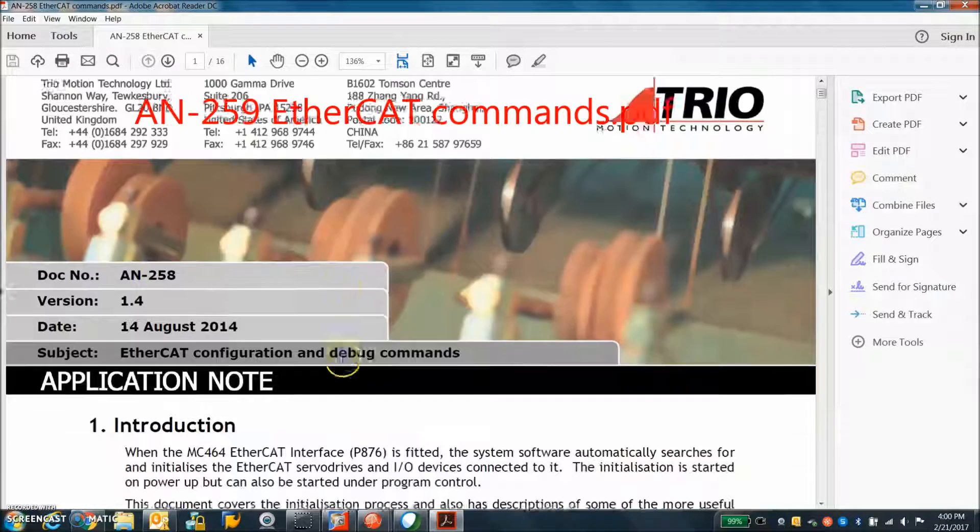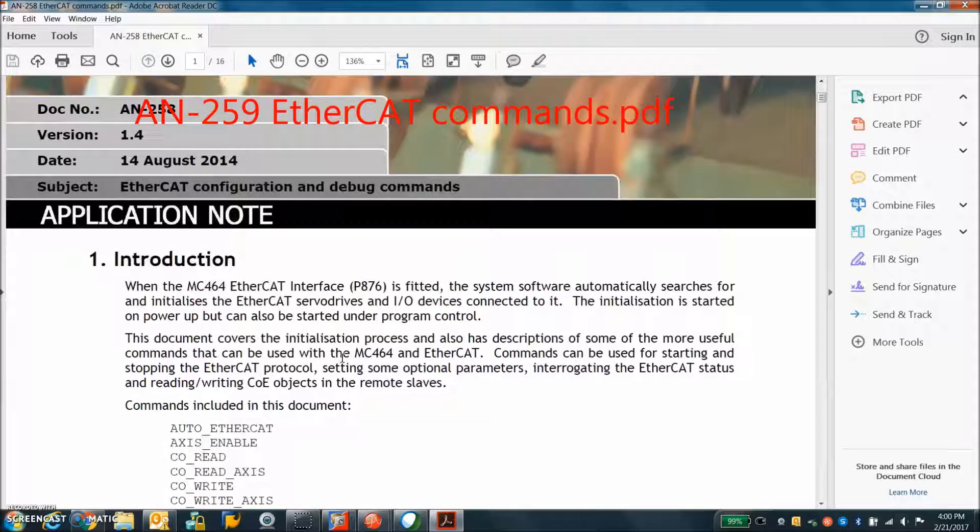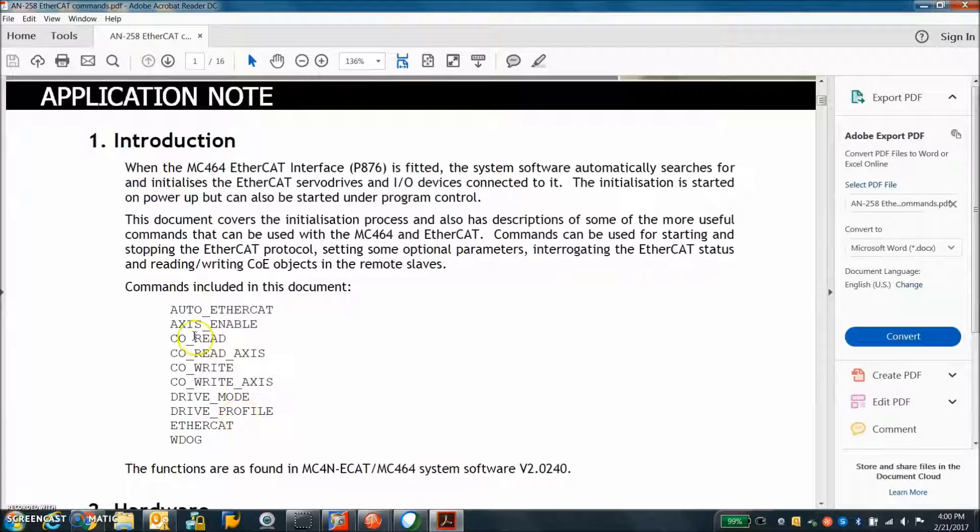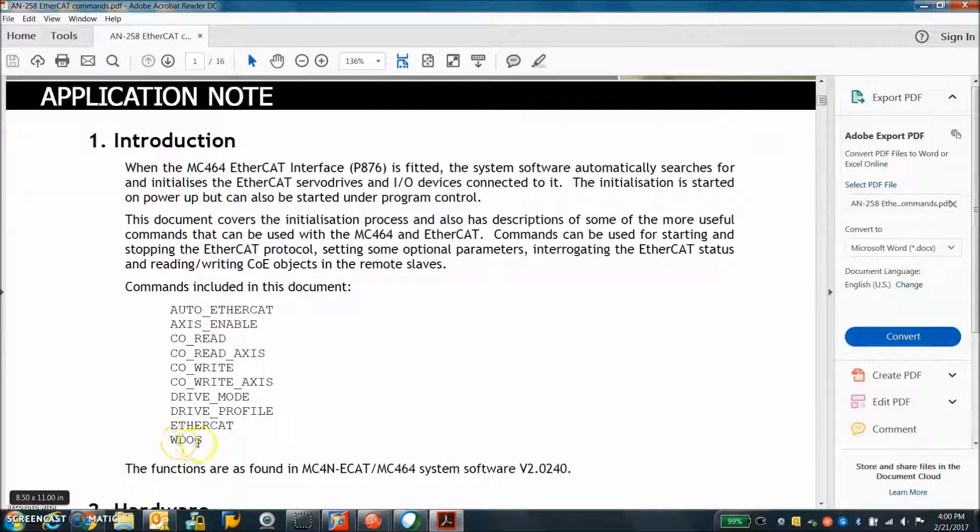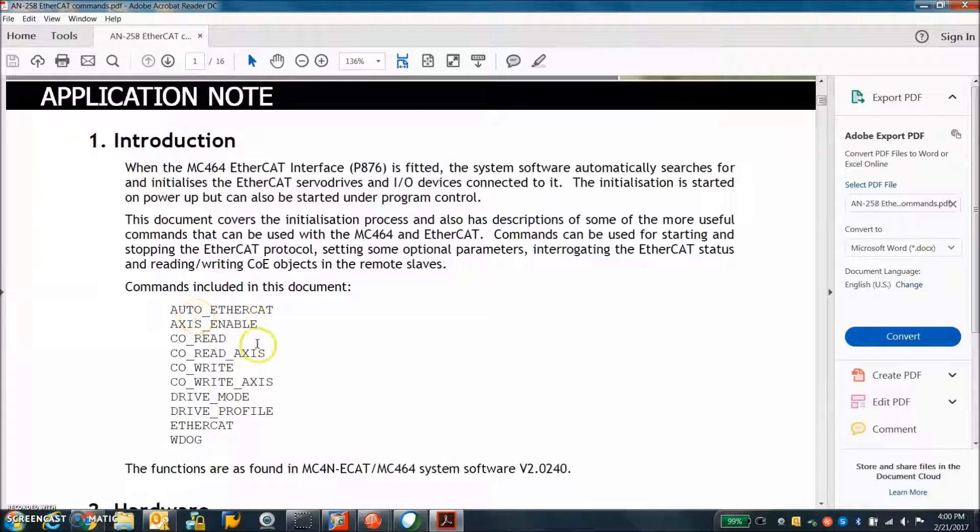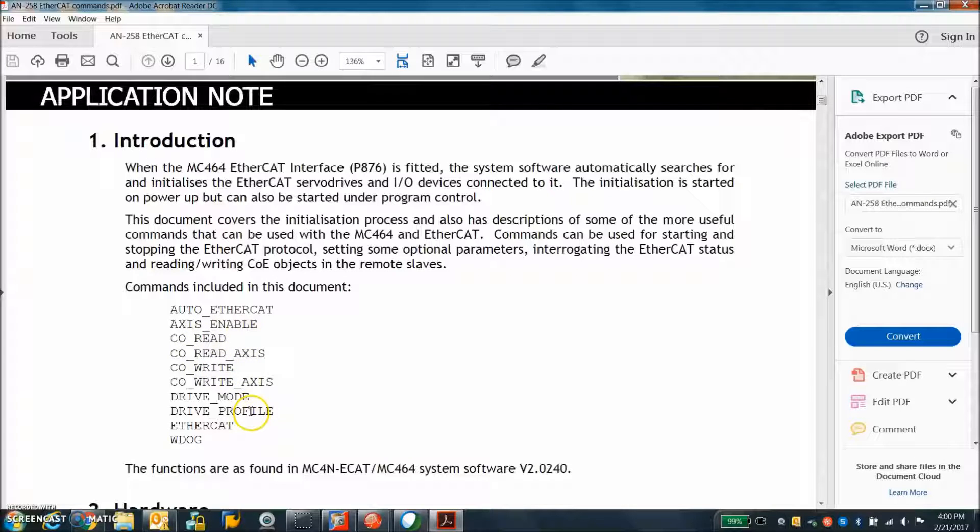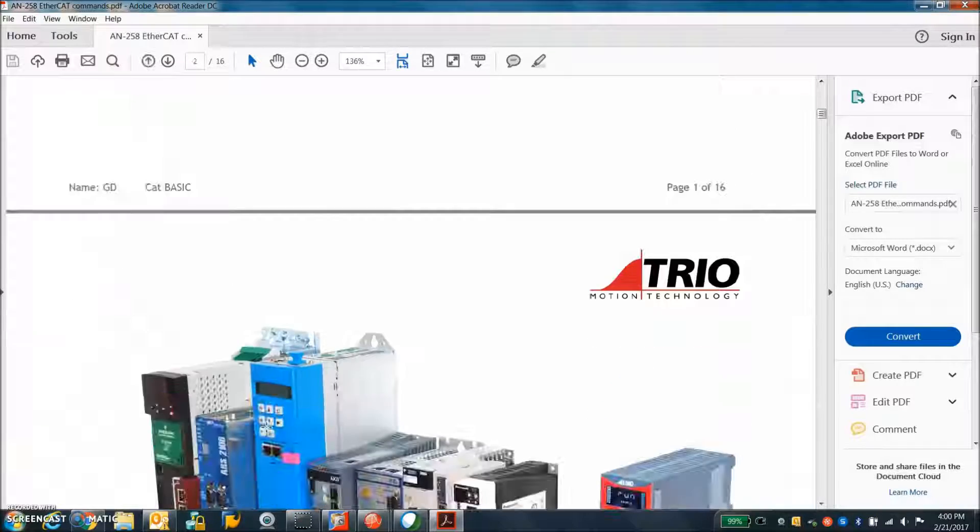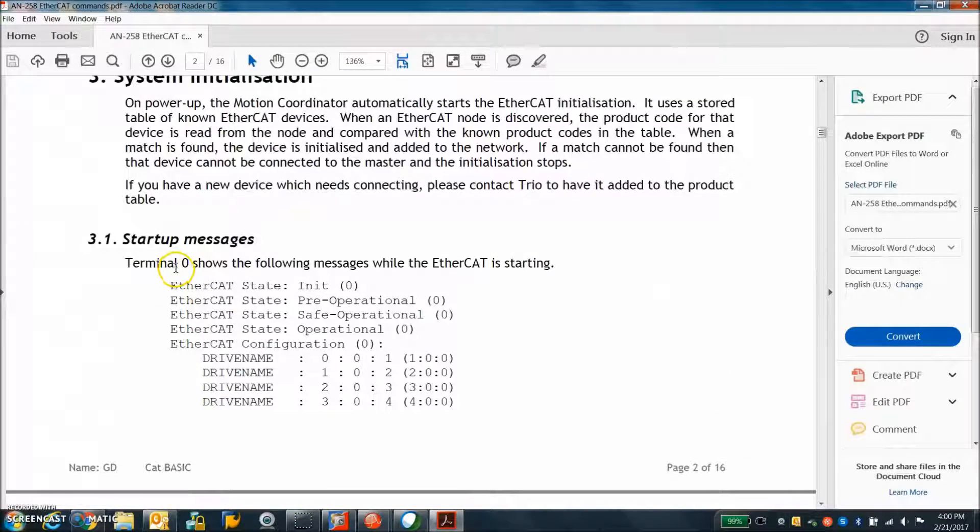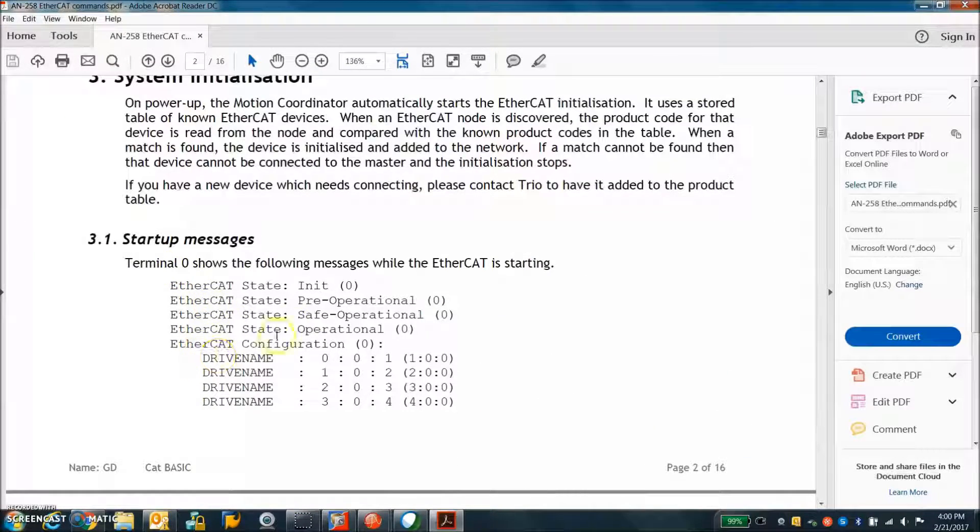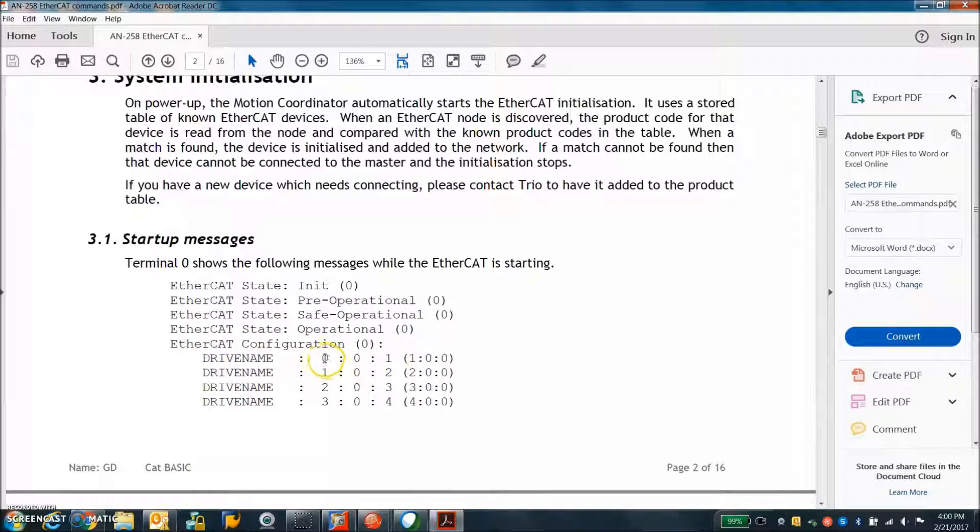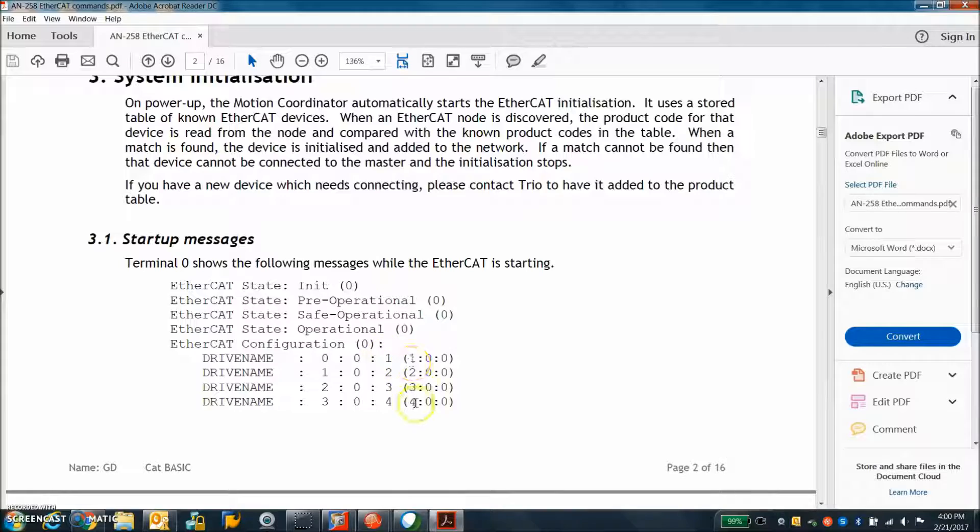Take a quick look here at the controllers. The MC_CONFIG file has limited things that you can do. Watchdog EtherCAT, that's that EtherCAT 0 0 command so we can turn on a watchdog. We can auto EtherCAT on power up or we can assign addresses. So here's an example of the EtherCAT coming up with, we could have several Copley drives starting at node 0 1 2 3 and then there's the aliases and the assignments.